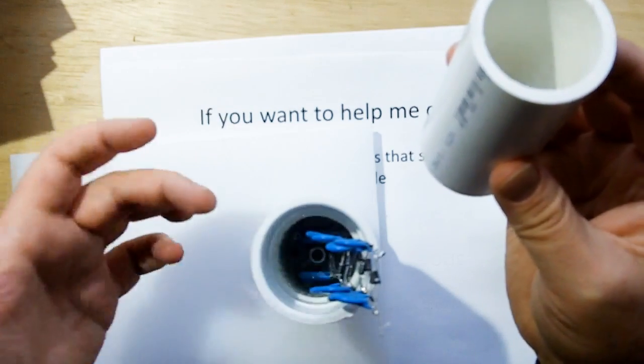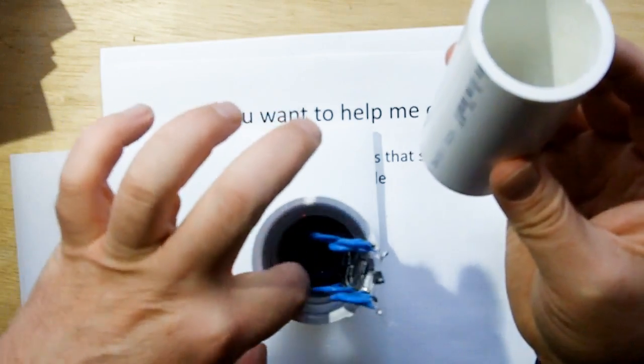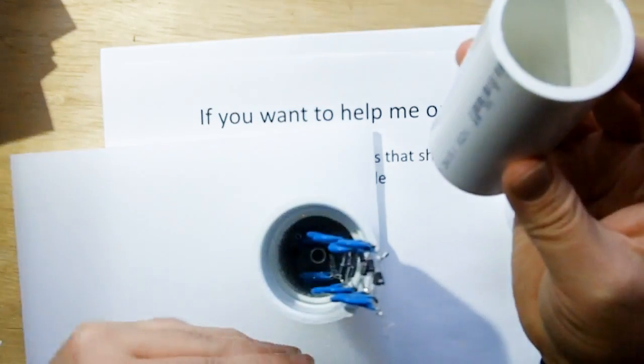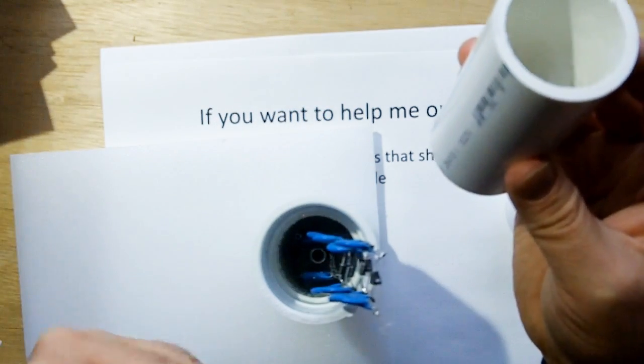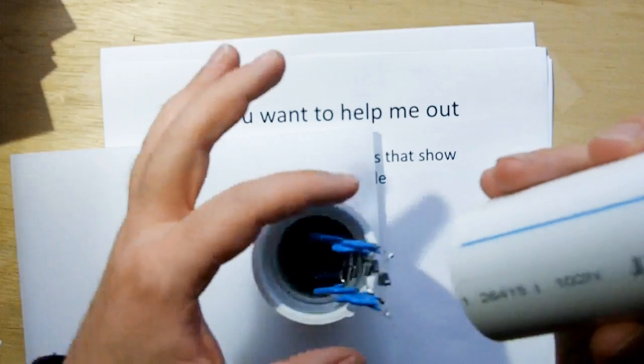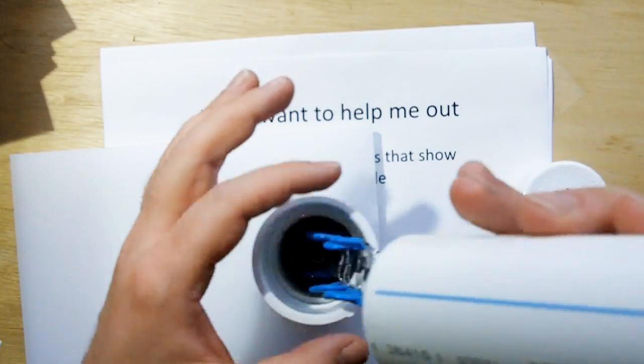I've separated it at the 6 kilovolt mark, put an insulative disc in here to separate the two halves so they won't be arcing between them. Hopefully that keeps the arcing down - I might have to separate it at different strata.